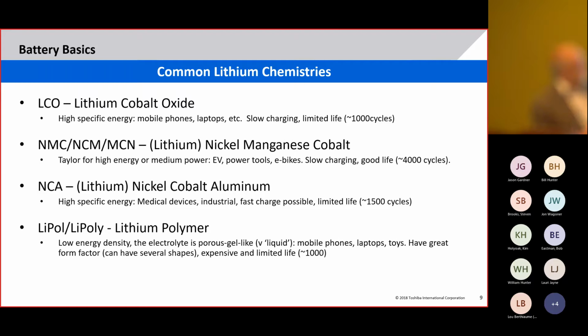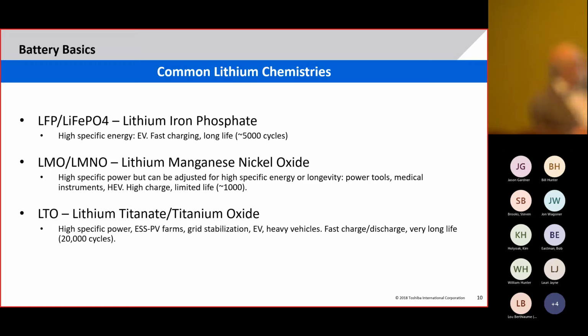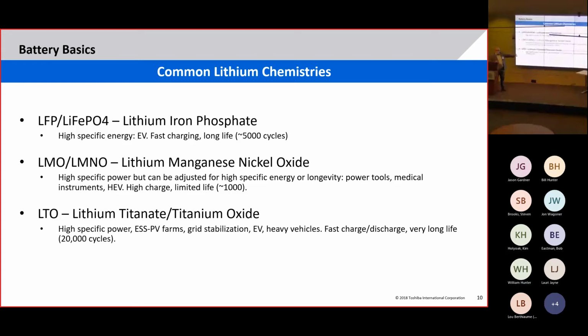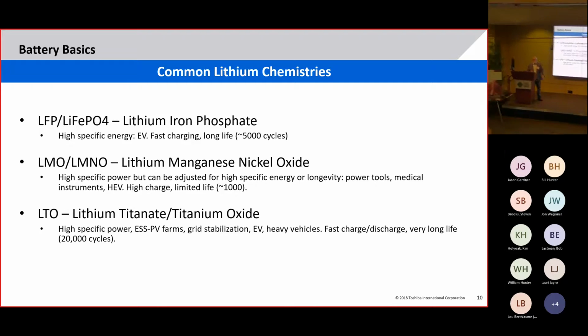I want to draw your attention to NMC, how many cycles? It's about 4,000 cycles, give or take. LFP is about 5,000 cycles. VRLA, I'll say 500 cycles because it varies between 350 to 600. So let's just say 500 cycles. You can see you get a tenfold increase in life cycles between VRLA and lithium-ion batteries, and that's one of the advantages. The other one is LTO at the bottom, that's what Toshiba makes, that's 20,000 cycles, hence the repurposing of the batteries.